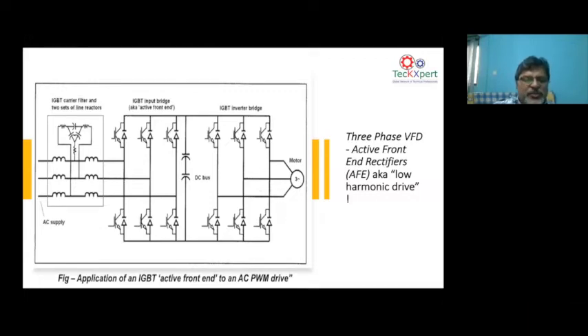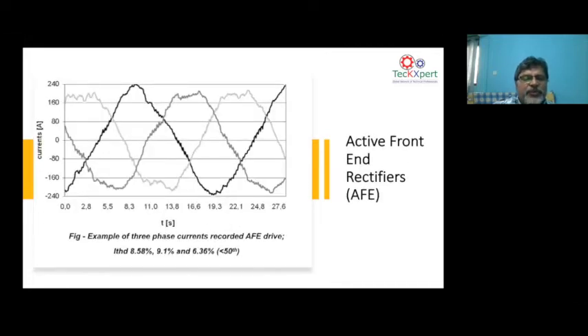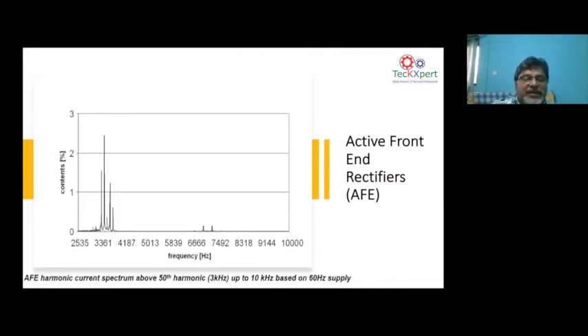Go to the next slide. The active front-end drive, as you can see here, shows an example of how the active front-end reduces the harmonics. Go to the next. But at the same time, this is a very important slide. You can see here, when an active front-end drive is put in, you have harmonic frequencies at 3361. That 3361 relates to more than 3,500, which relates to more than the 50th harmonic.